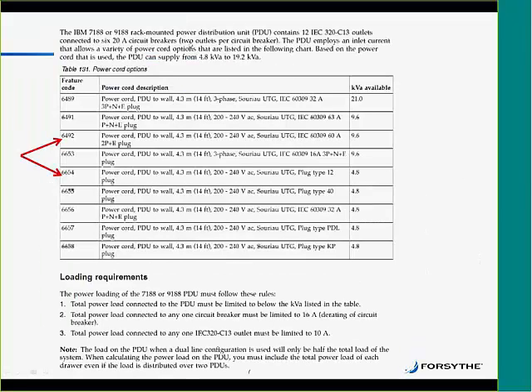All right, so this is right out of the Red Book, where it actually says that we have these 20 amp circuit breakers, and basically the different line cords and what they can handle. So you can see this is the three-phase one up the top here, and it can handle up to 21 kVAs. But the 6492 is your 9.6, and your 6654 is your 4.8. So it's probably better to do the sizing in kVAs. Then there's a whole bunch of other ones depending on whether you want to have special connectors and plugs and so on. So that's how you do the basic sizing.